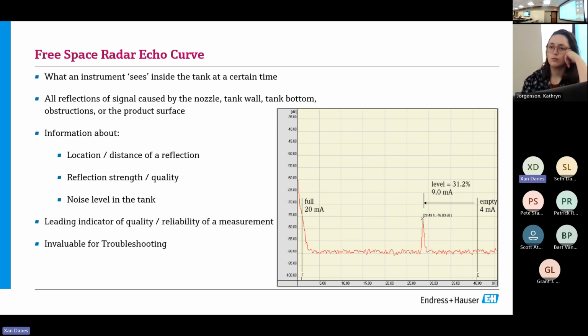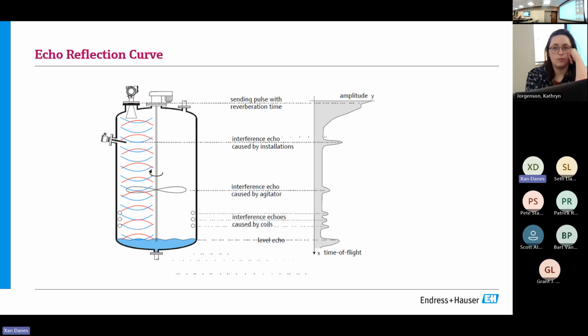It gives me information about the distance—how far away the reflections are—and the strength or quality, the amplitude of the reflection. It also shows me the noise level. So it's almost like a signal-to-noise plot over the full span the device is set for. This is our leading indicator for quality and reliability of a measurement, and it's invaluable for troubleshooting, being able to see exactly what the device is seeing.